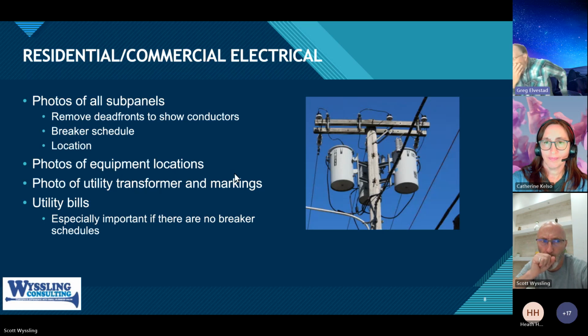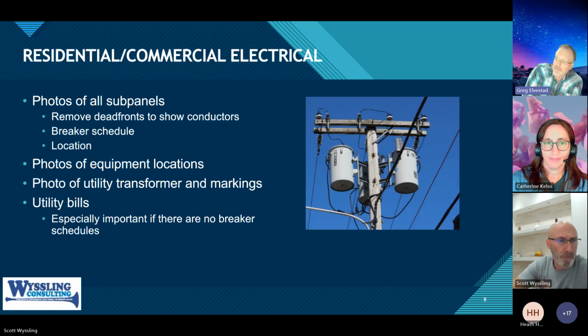Utility bills to calculate load is very important. A lot of times a utility or an AHJ will want to know how much load is on this property, and whether the service or the PV size you're proposing is way oversized for their consumption, or in line with it. So we have to do load calculations for that. There's a number of different ways to do that.